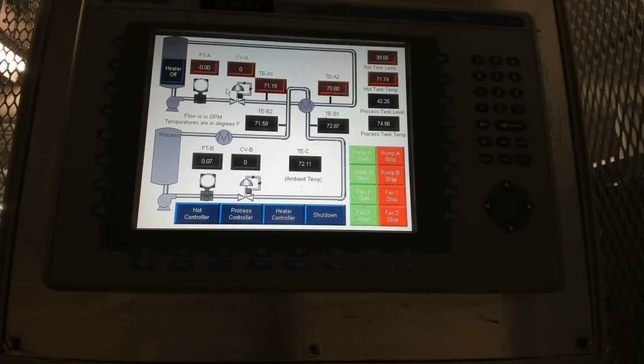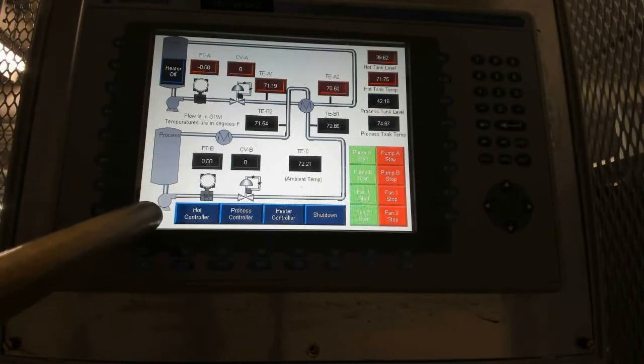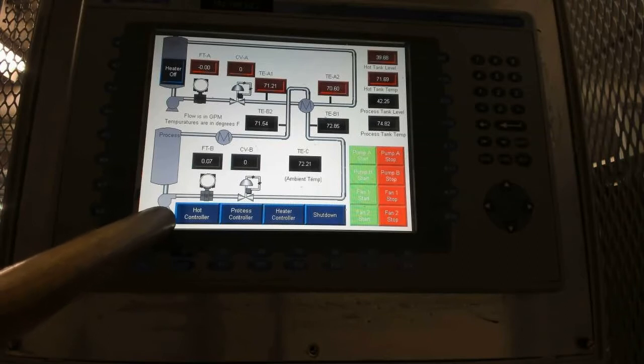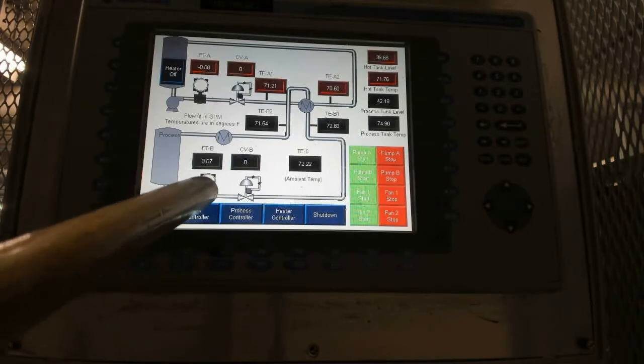Here we have the human-machine interface, commonly referred to as the HMI. The HMI is the location where an operator or a user would interface with the system. So you can do set points, monitor system variables from the human-machine interface. You can see that there's a pictorial representation of how the system is laid out. Because when you actually look at the physical system, it can be a little bit confusing, but this will lay it out nicely.